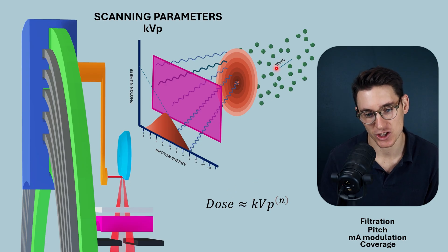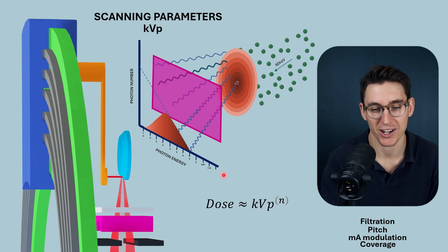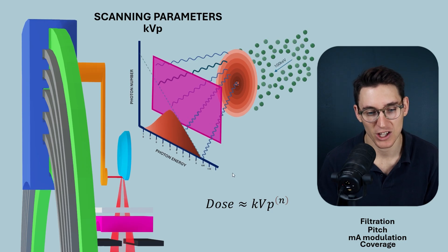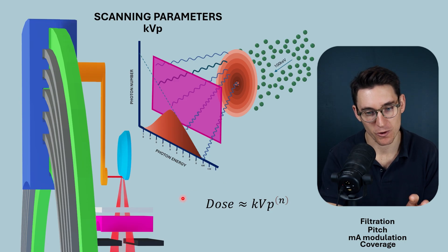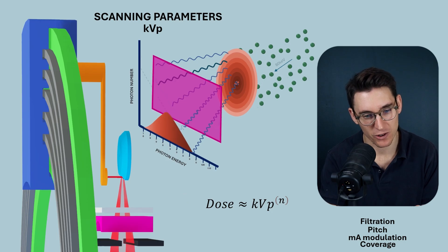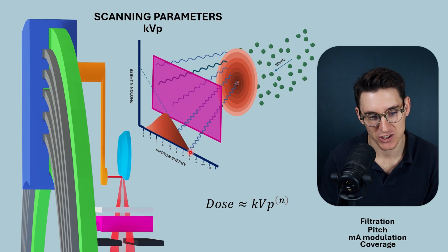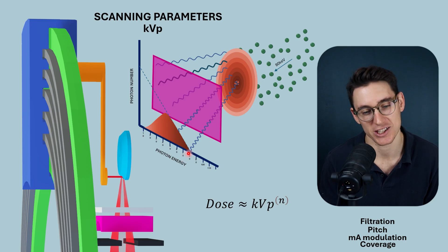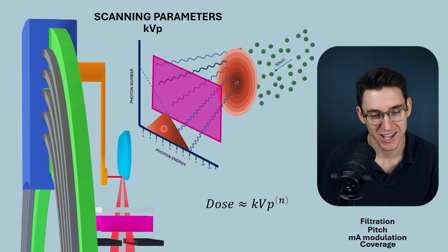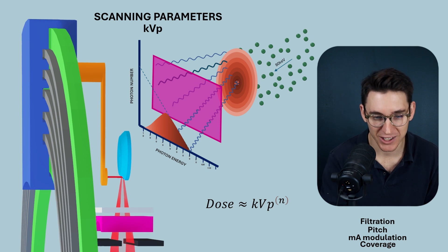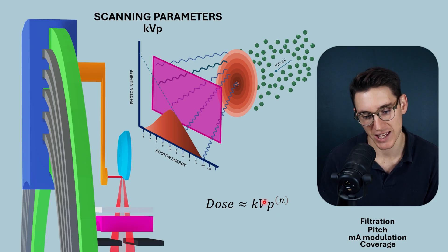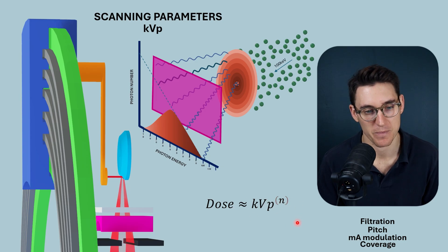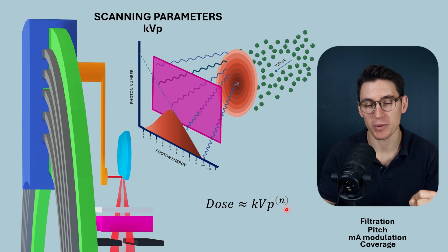Watch what happens when I change the KVP from 80 keV to 100 keV — see how the x-ray spectrum has shifted and the area under the curve has changed. Going back from 100 to 80, our graph gets much smaller: our maximum photon energy gets smaller, the area under the curve gets smaller, and as a result the dose gets lower. As we increase KVP, we increase dose to the patient, roughly proportional to KVP to the power of 2.5 or 2.6.